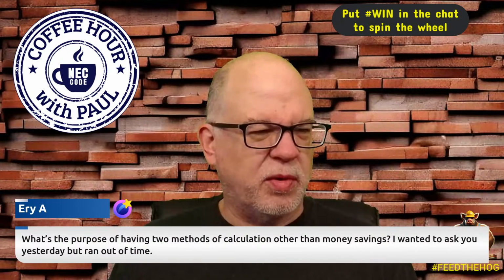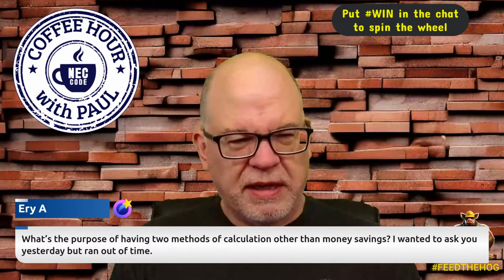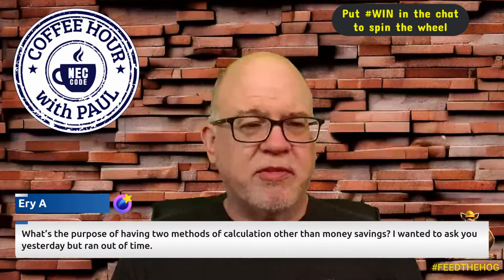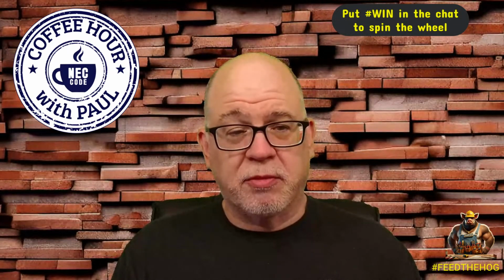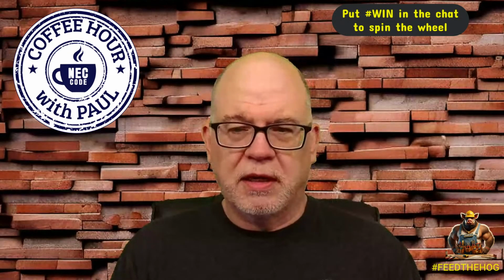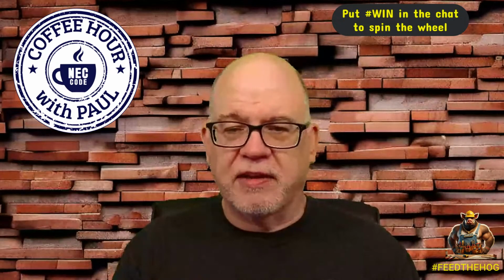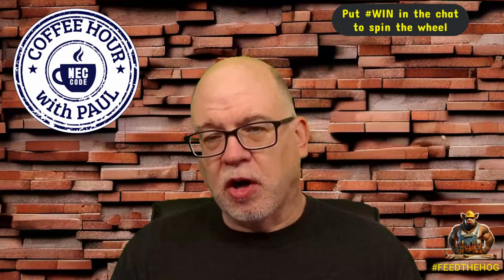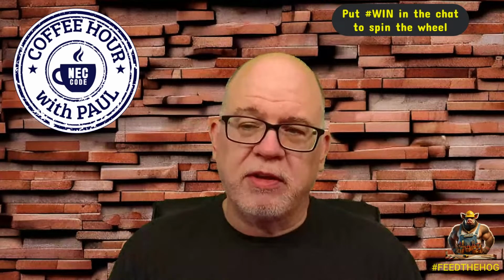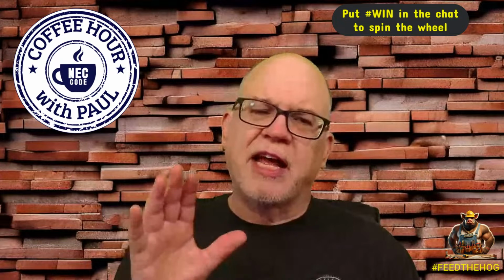Ery's got a question this morning. It says, what is the purpose of having two methods of calculation other than money savings? I wanted to ask you yesterday, but ran out of time. You mean the traditional method versus the optional method? The optional method takes into account diversity, no different than the standard method. We need the standard method for sizing neutrals. There are some occasions where the standard method may yield a better result, but I wouldn't say the NEC cares about the money. It's not a money thing.